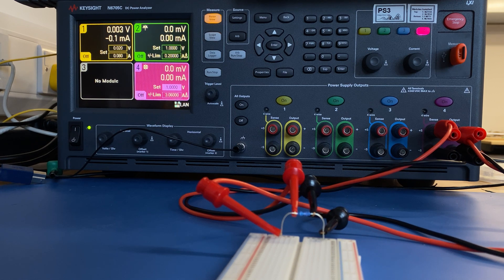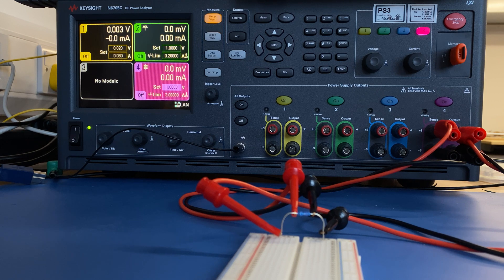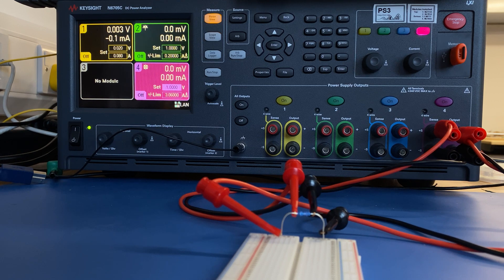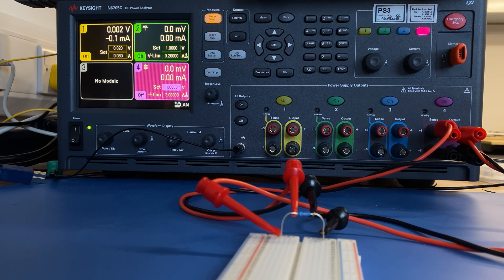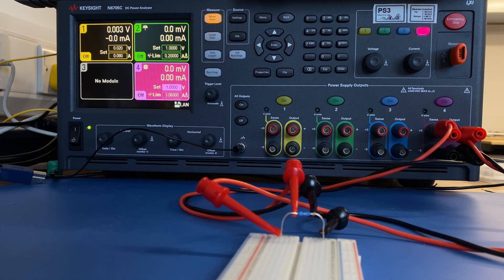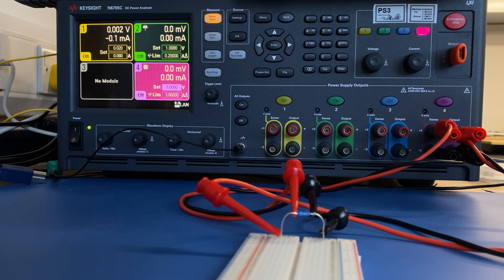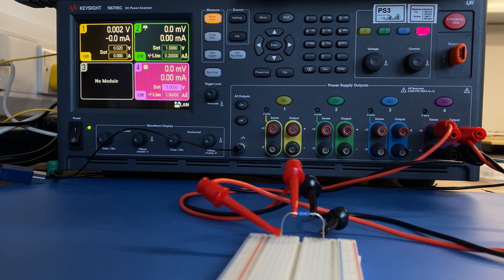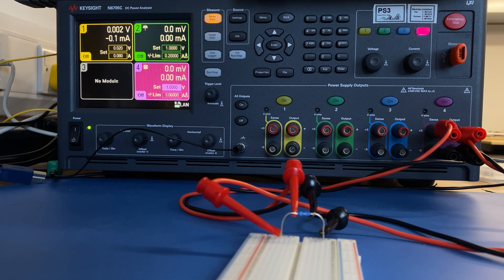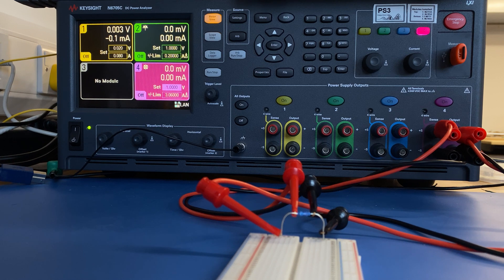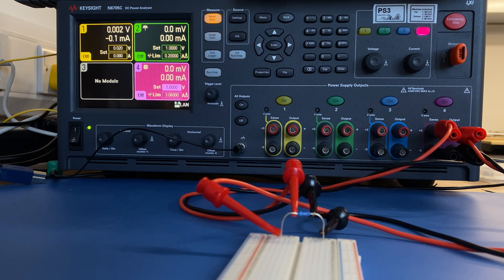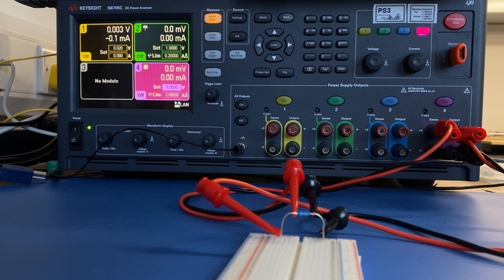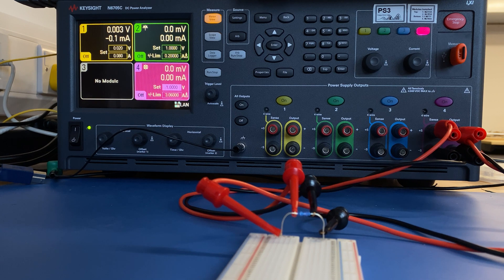If your instrument supports 4-wire, you should always use this mode because it's stress-free to use. The instrument can take care of everything for you and it's accurate. It can compensate the voltage drop in your output.